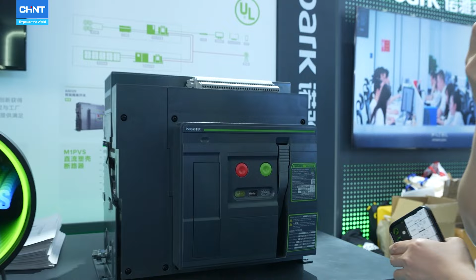The maximum voltage can be up to 1,500 DC. The current rating is from 800 to 2,500 amperes. The short time withstand rating is 150 kA, which ensures it is not damaged before the fault current is cleared in the circuit.